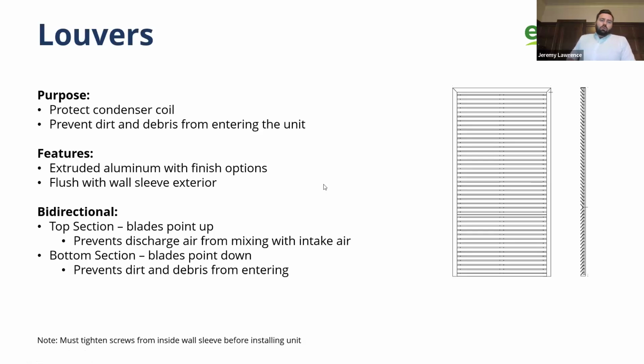Keep them coming. So the louvers are part of the system. They are an opposite deflection between the fresh air coming in and the exhaust air going out, so we don't get any recirculation, and that leads to the typical 10 feet separation between fresh air and exhaust air on an ERV. So these units are part of the system. We have had customers ask if they could get their own grills. They certainly could, but they'd have to be exact to this because the grill design is part of the airflow of the system, and if you had the wrong airflow, we could actually change the capacity of the unit.